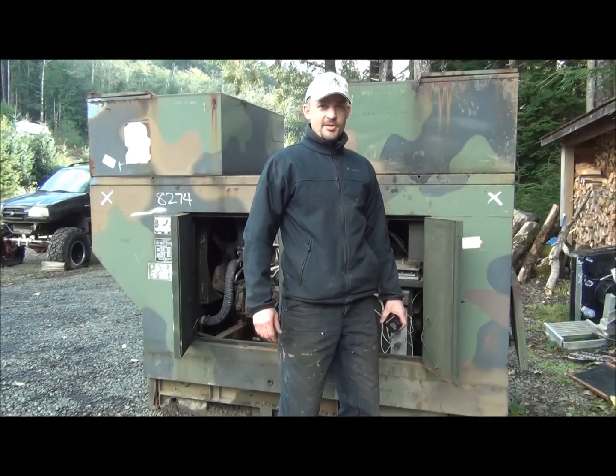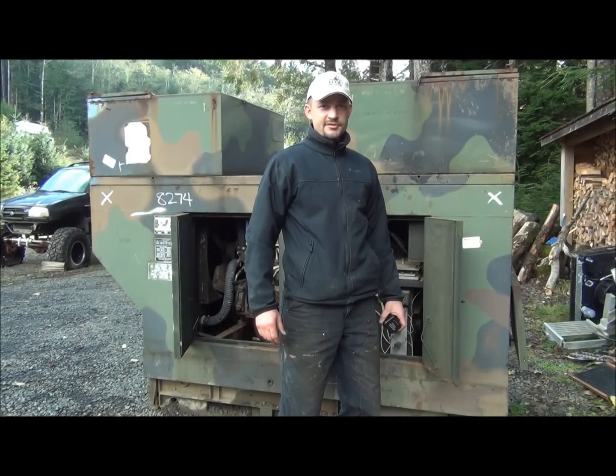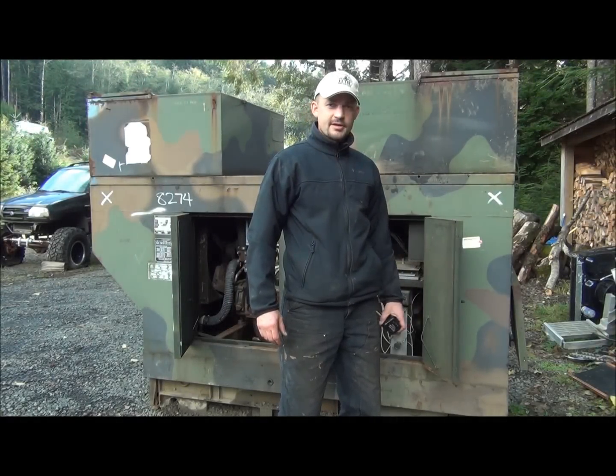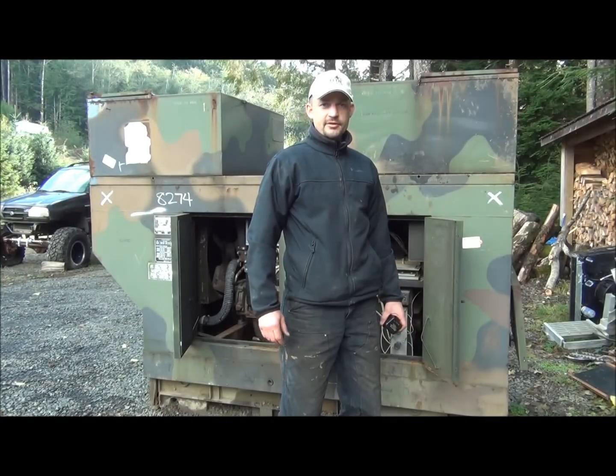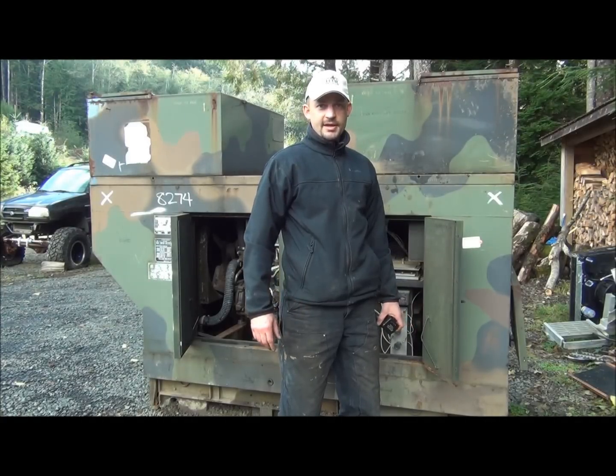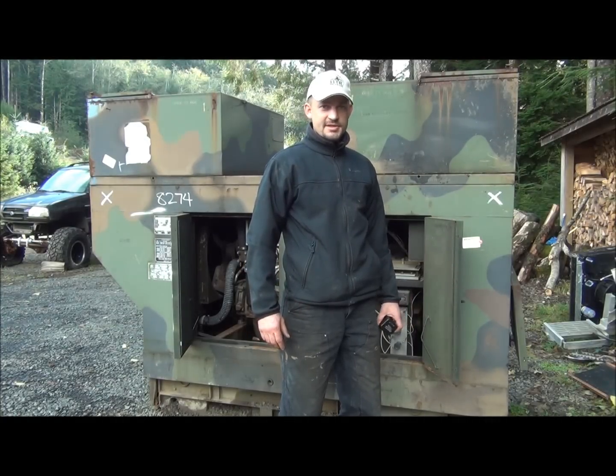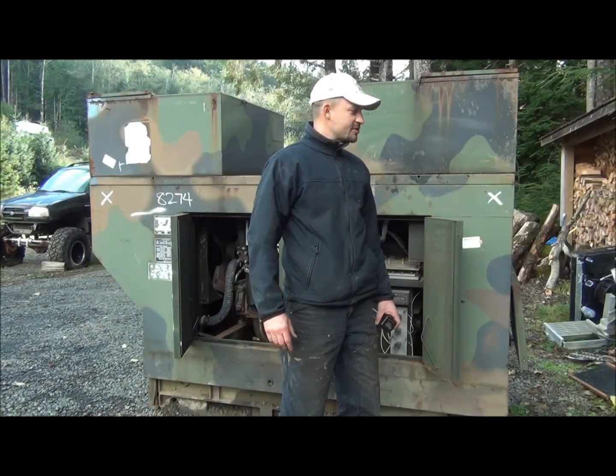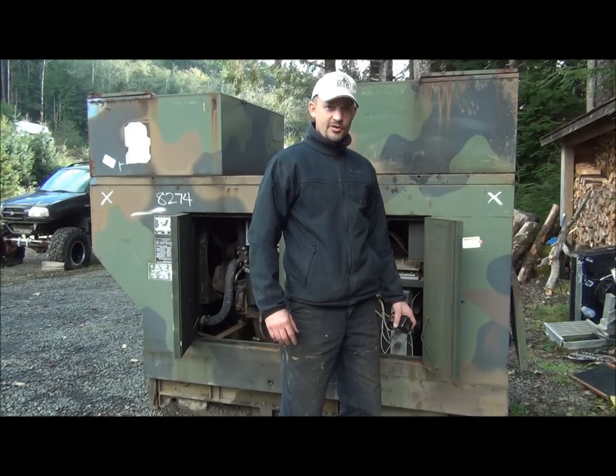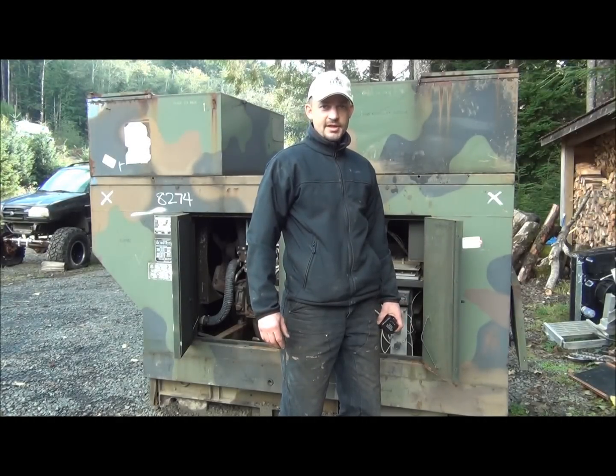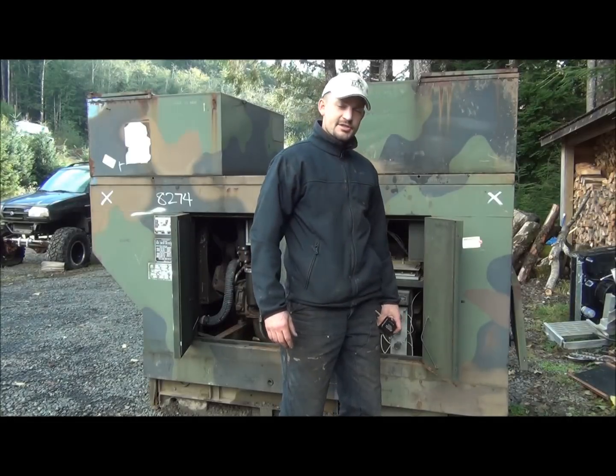I went through my bin of spare parts, and I managed to come up with a frequency transducer that'll work in this generator. It's an adjustable type, so I was able to install it in here and bring it into adjustment to match the existing meter that's in here. I set it up so it indicates the proper frequency all the way from 45 up to 65 hertz. So I verified that against my digital voltmeter.